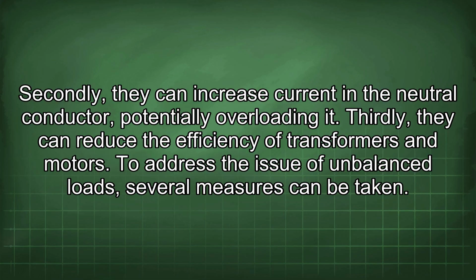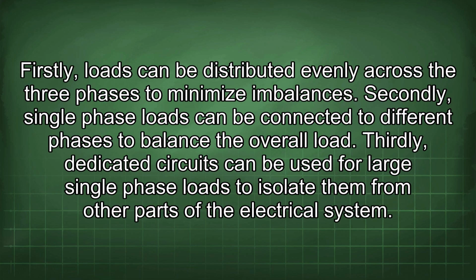To address the issue of unbalanced loads, several measures can be taken. Firstly, loads can be distributed evenly across the three phases to minimize imbalances. Secondly, single-phase loads can be connected to different phases to balance the overall load. Thirdly, dedicated circuits can be used for large single-phase loads to isolate them from other parts of the electrical system.